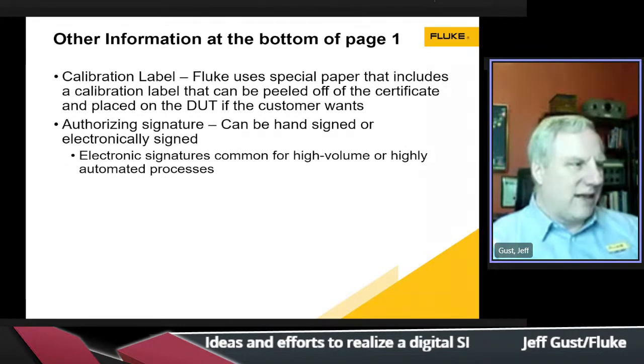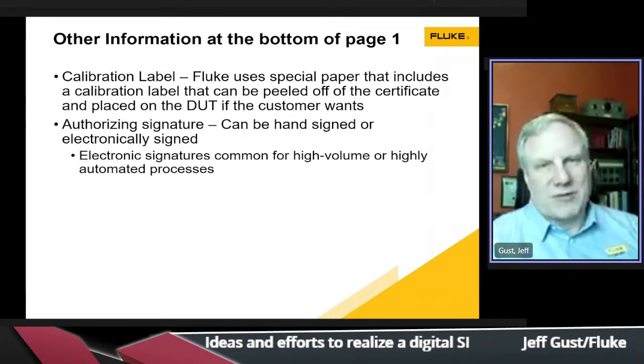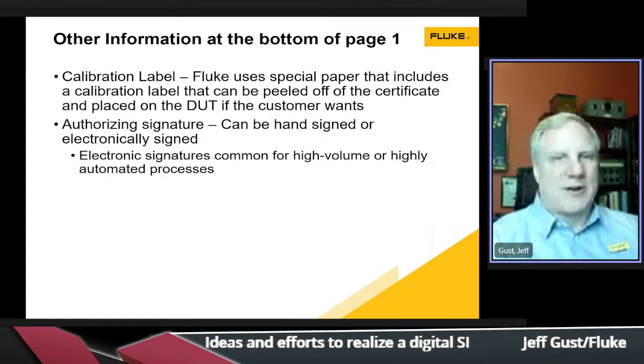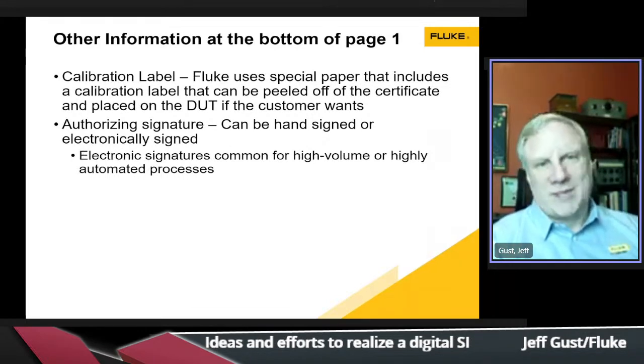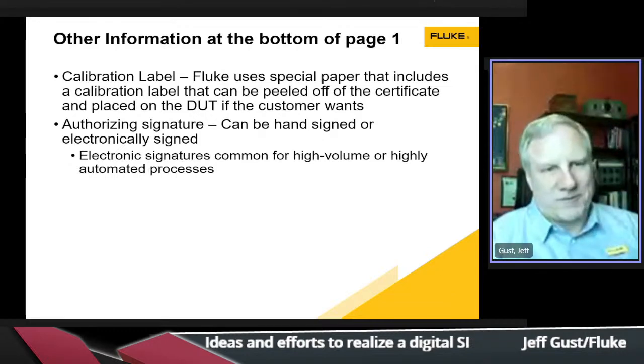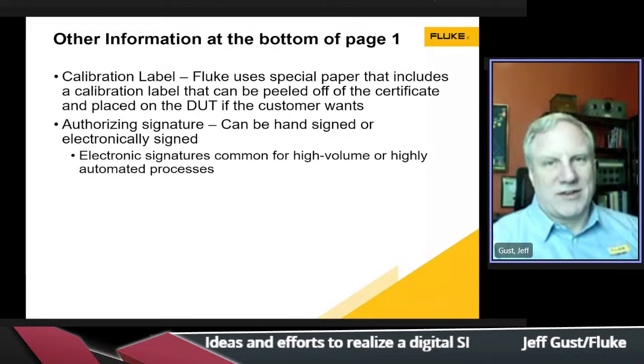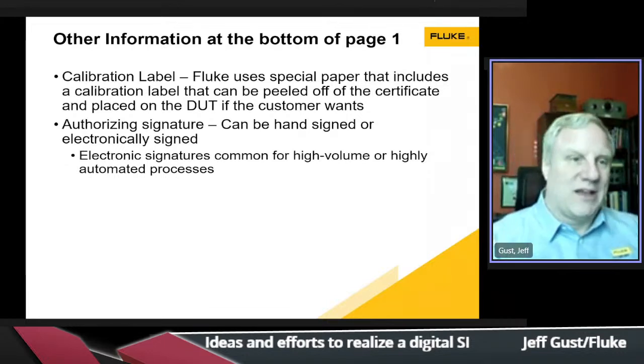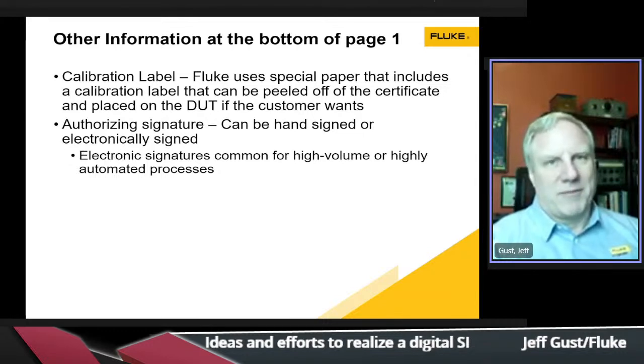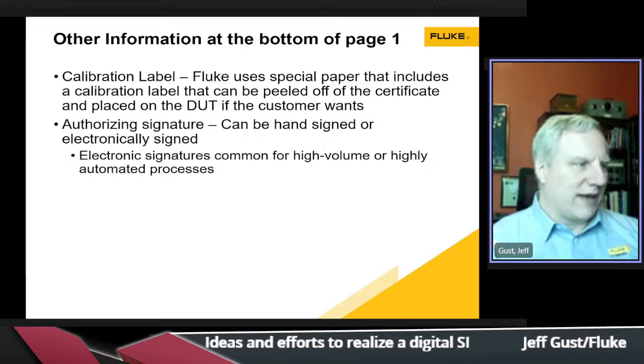We included a special paper where the label is embedded into page 1 of the calibration certificate, so that it has a calibration label that can be peeled off of the certificate and placed on an instrument if the customer wants, or they could leave it right there on the certificate, because some customers have their own calibration due dates and labeling in their laboratories that they want to use. We also found that no matter where we decide to place a calibration label for the customer, we're usually wrong, because they may put it in a rack configuration, so the label may not be visible, or everybody has where they would like to place the calibration label. So we allow the customer to do what they want to do on that.